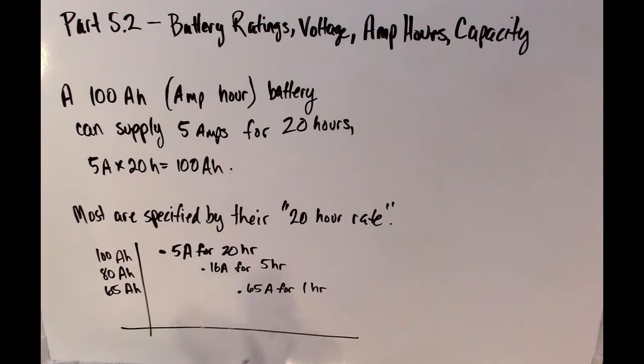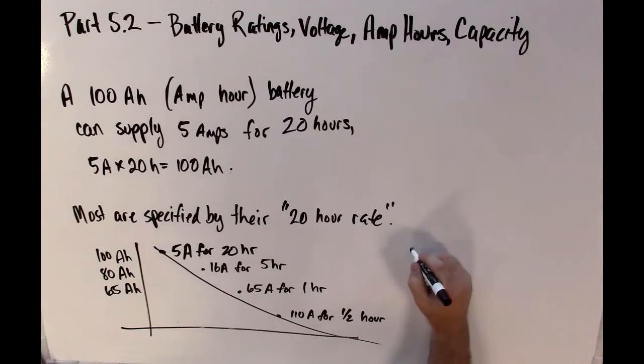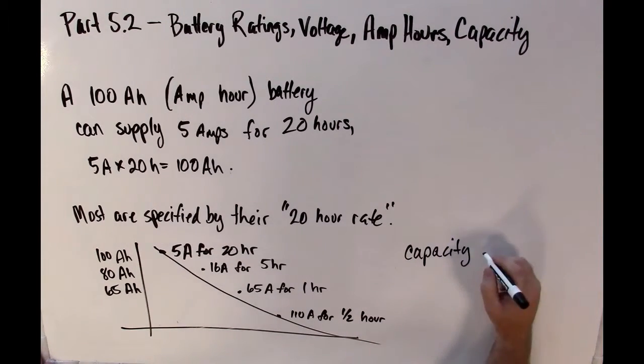But if I take that same 100 amp hour battery and discharge it at a faster rate, such as at 16 amps, or 65 amps, or 110 amps, what I'll see is the overall capacity will decrease. It won't hold as much charge if I take the charge out at a faster rate.